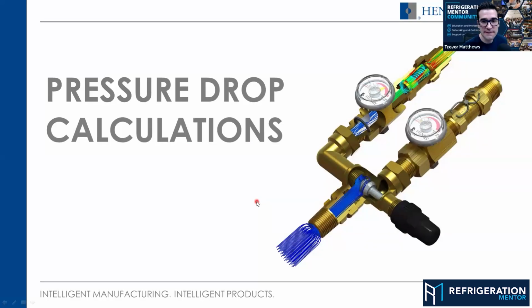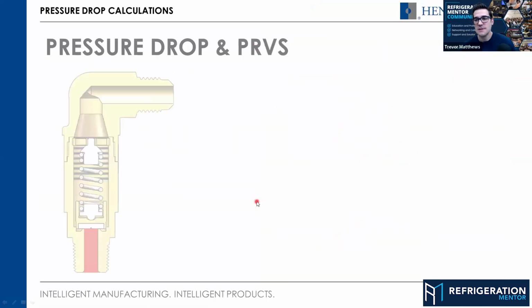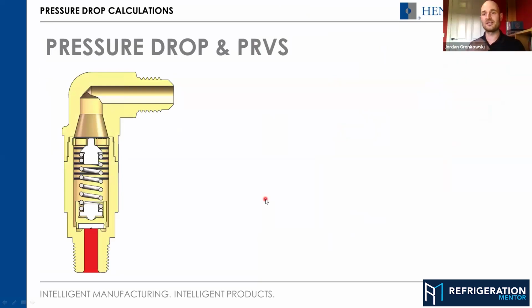No, I think that's pressure drop calculations. So pressure drops in PRVs. Why is it important? We talk about pressure drop in the inlet line, pressure drop in the outlet line. Why is that important? So this is a typical straight-through PRV with an angled outlet on the top. This is when the valve is closed. This is the normal condition that the valve will see all the time. Coloring pressure here. So red is high pressure.